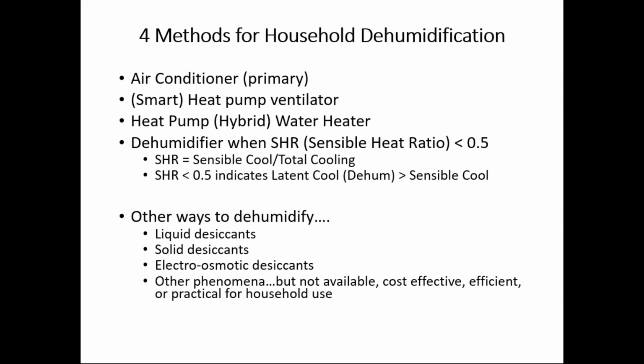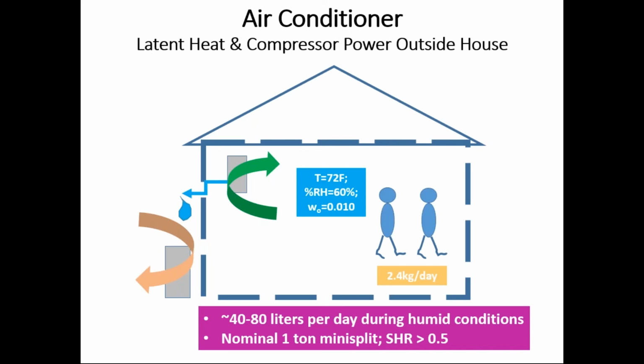But we'll discuss that. These other ways have been studied for decades, if not centuries. There are other ways to dehumidify, but these are not readily off the shelf or cost effective or practical for household use, just to note that there are other means. Within an air conditioner, as a basis, we'll assume a one-ton mini split that's typical of the ones you find on the market today. These will remove somewhere in the range of 40 to 80 liters per day. So a 3-ton, say more of a central air conditioner, you might scale that up a bit more.